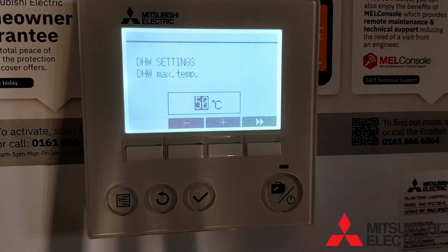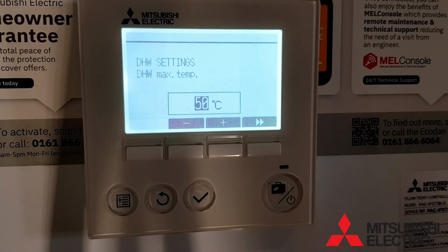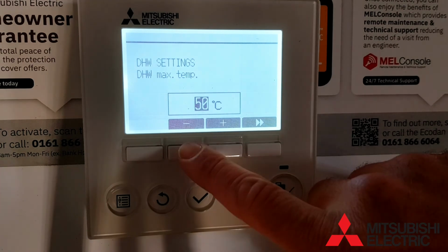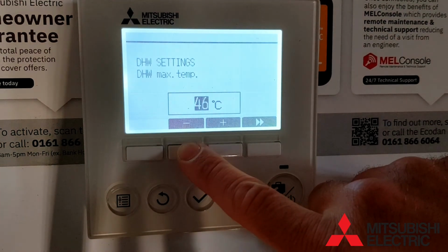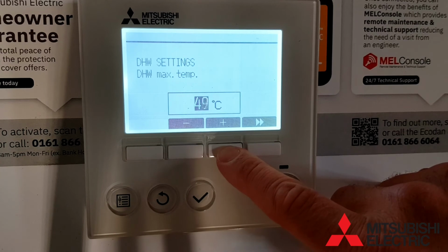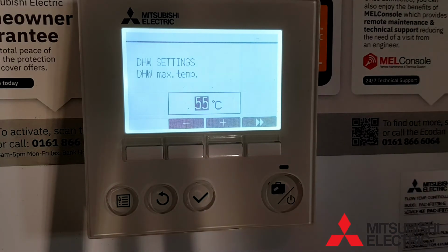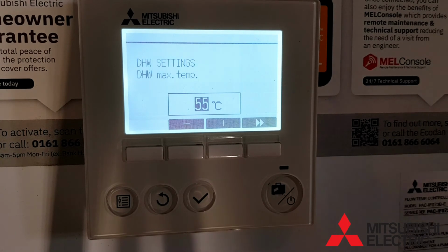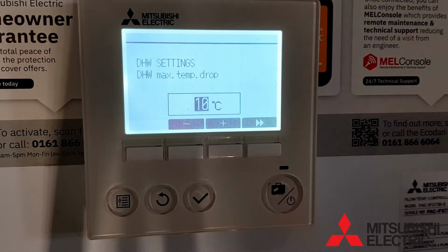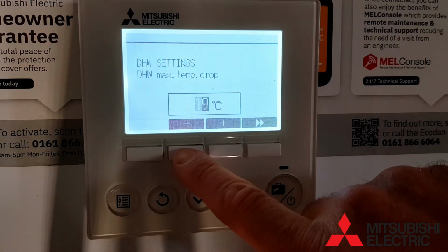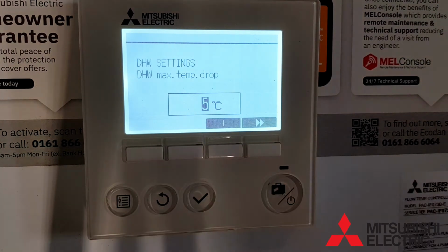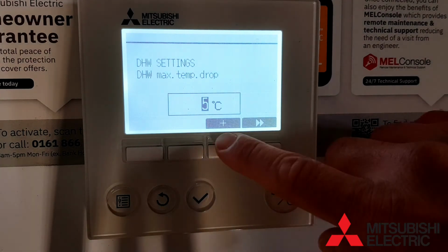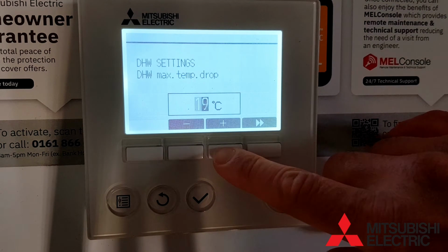This option is the cylinder hot water target temperature. It allows you to adjust this up and down. The recommended setting for the Mitsubishi equipment is 55 degrees. The next option is the temperature drop. This is the number of degrees the cylinder temperature has to drop before it will cycle back on another hot water cycle. The recommended setting is 10 degrees.